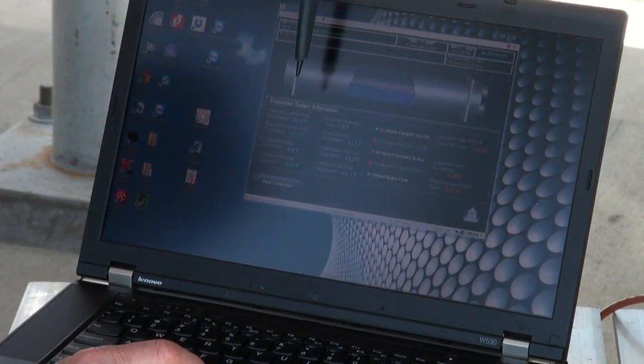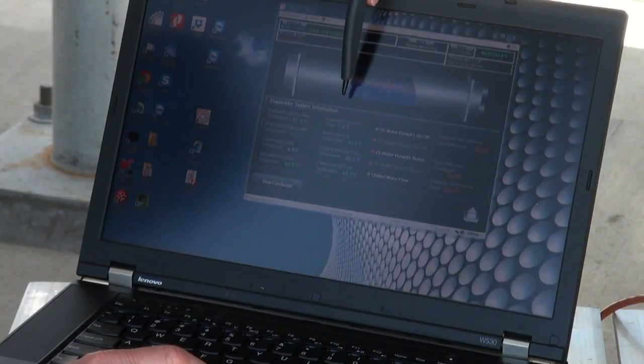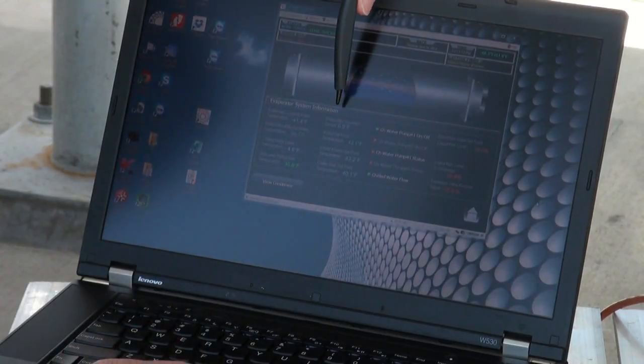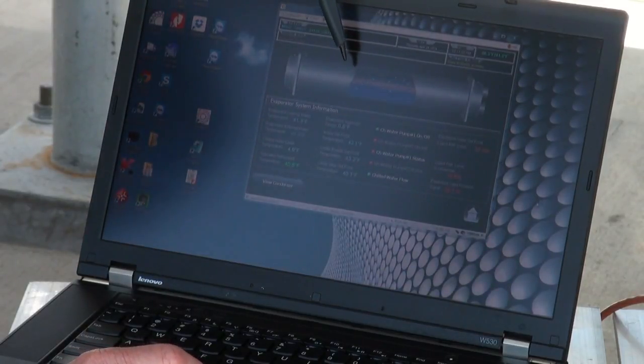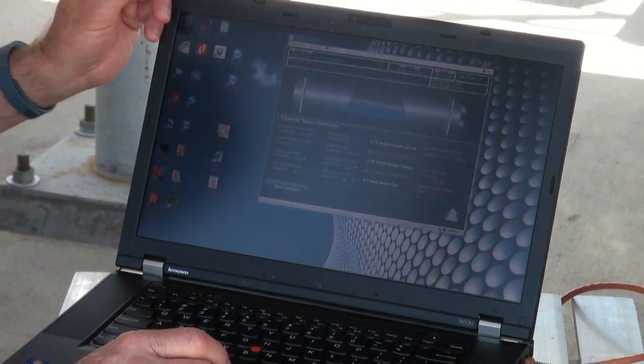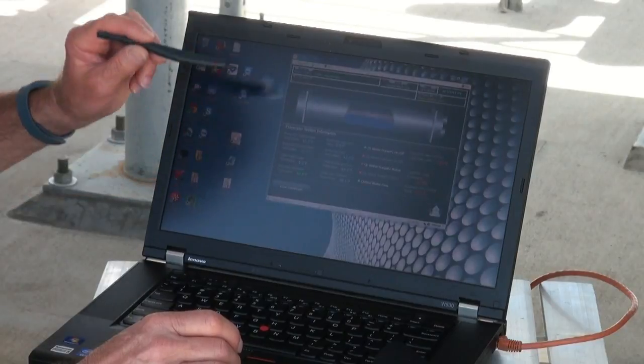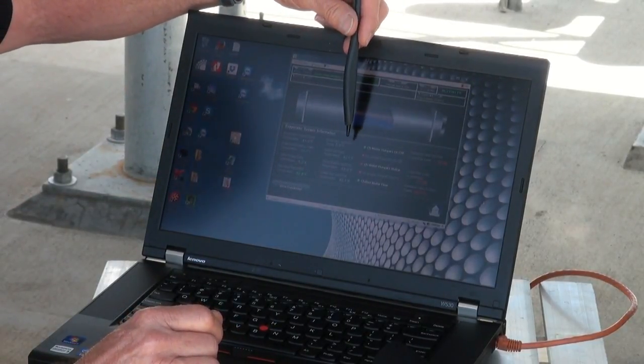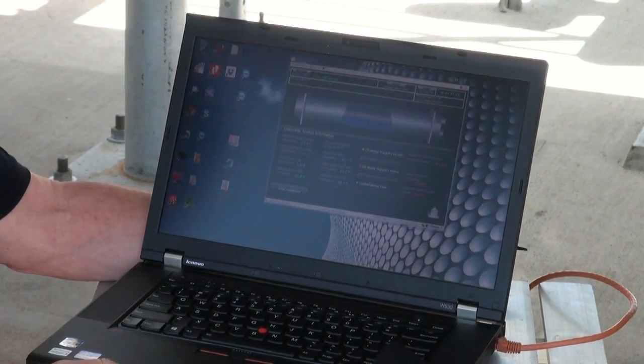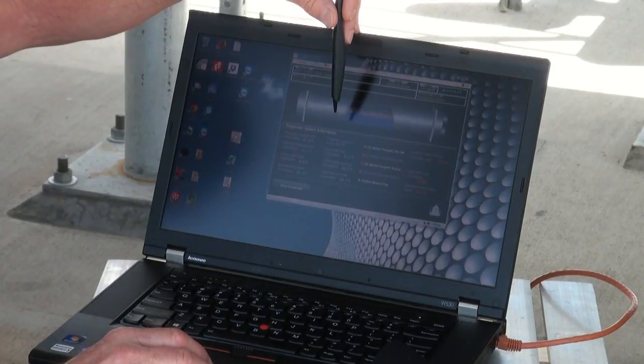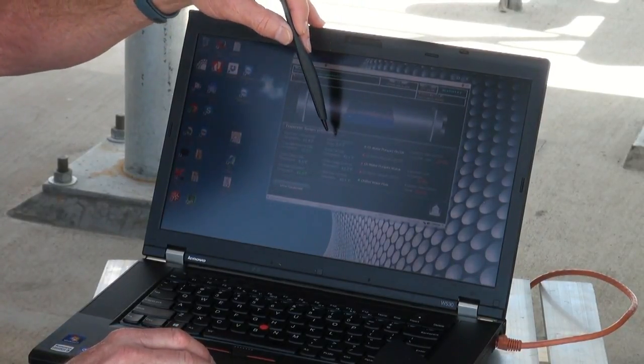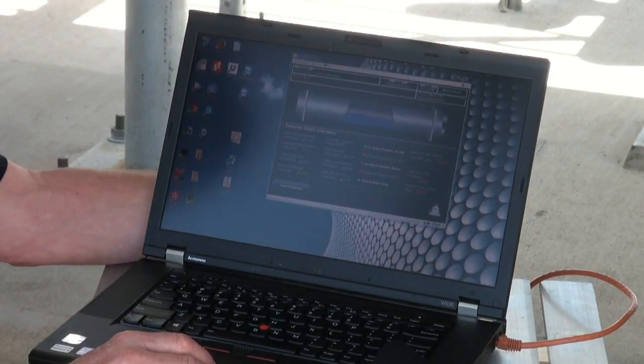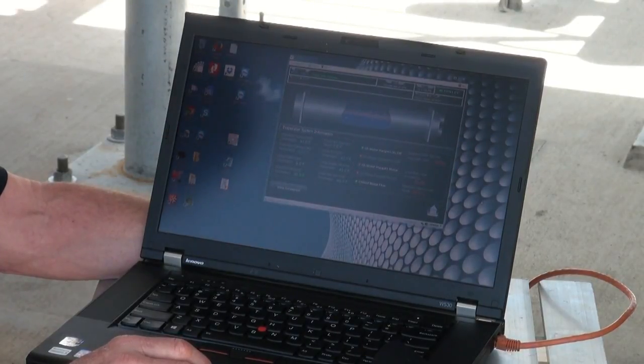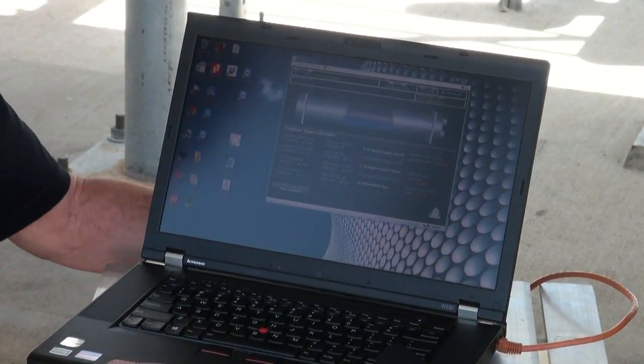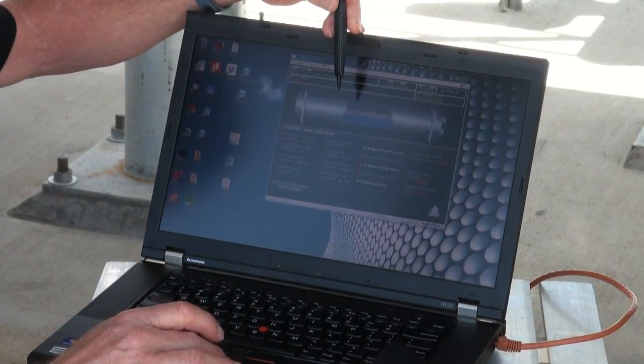Saturated refrigerant temperature. We've got the evaporator approach temperature. I don't know if you guys are familiar with that term. Approach temperature is the temperature difference between leaving water and our saturated refrigerant temperature. So the most efficient would be 0 degrees, so it'd be the same, but no chiller will do that. But we get very close, so it's very efficient. Typically what you see is anywhere from 0.5, 0.6 where it's running right now, all the way up to maybe 3 degrees during full load conditions. You might see it as high as 3, but typically it's much lower than that.